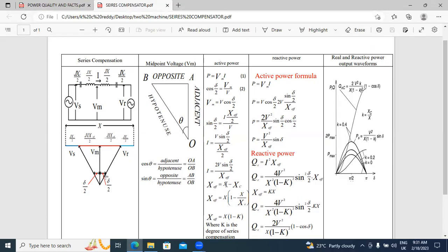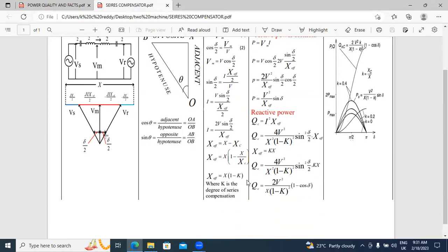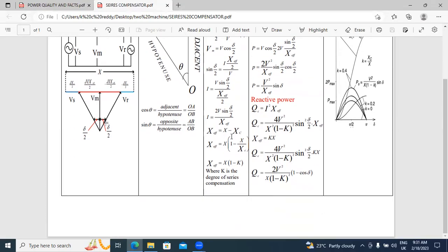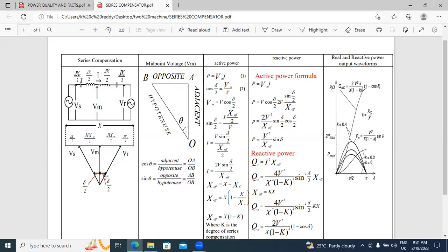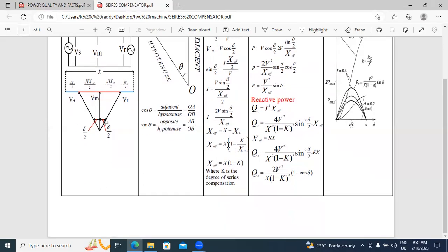X_effective equals X minus X_c, where minus X_c means minus the capacitive reactance value. Therefore X_effective equals X·(1 minus X_c/X). Finally, X_effective equals X·(1 minus k), where k equals X_c/X — k is the degree of series compensation.